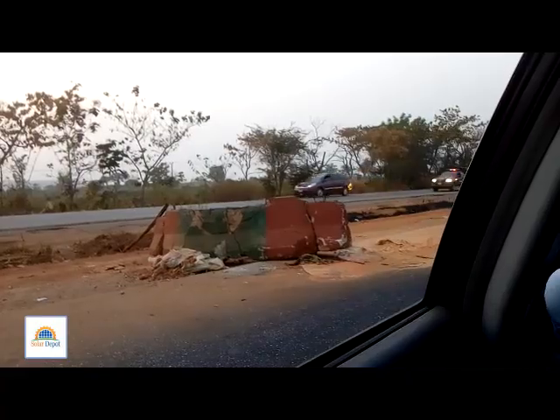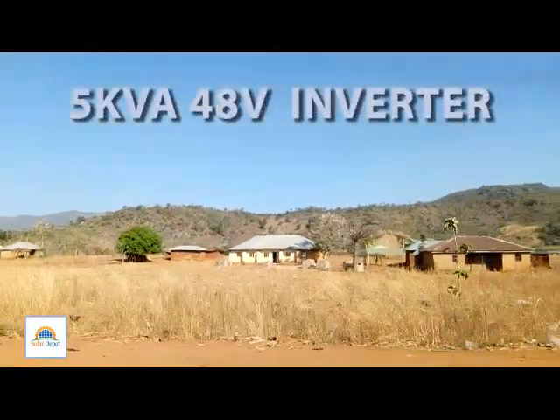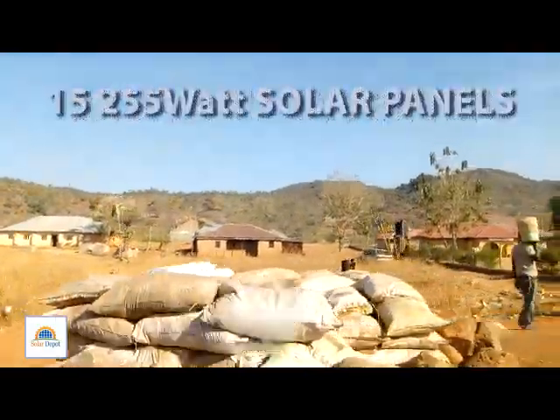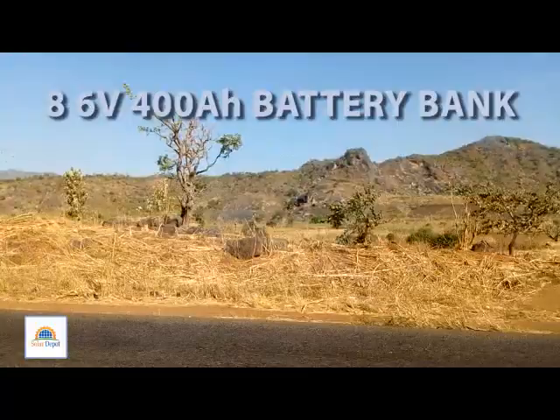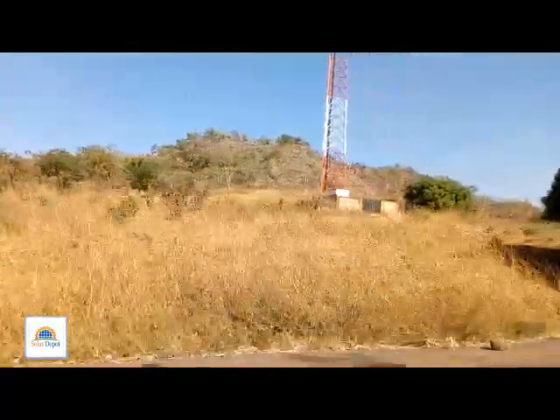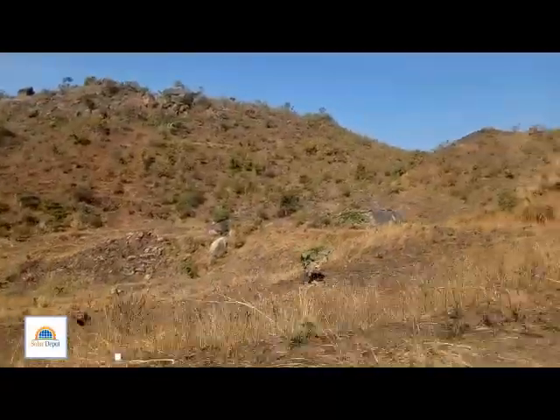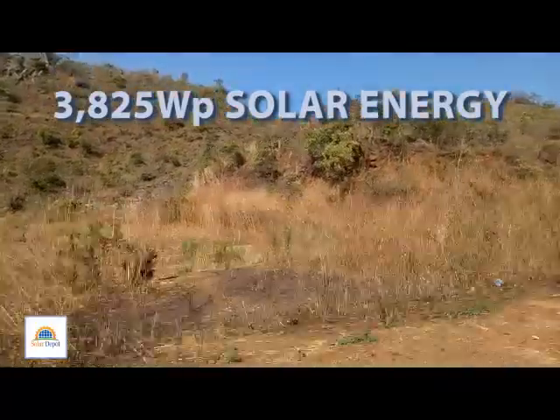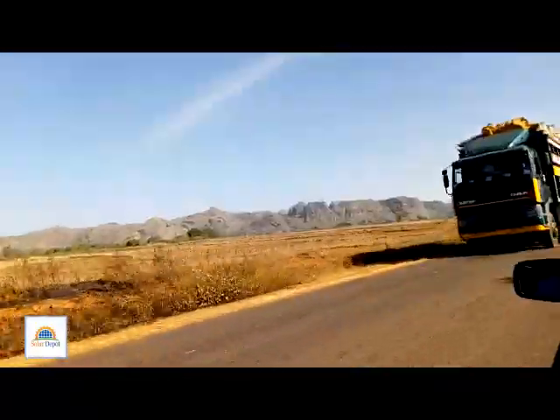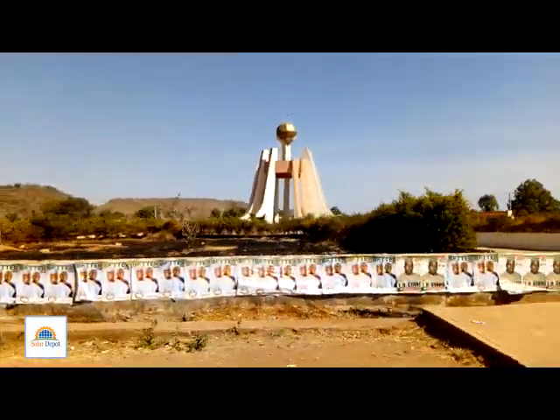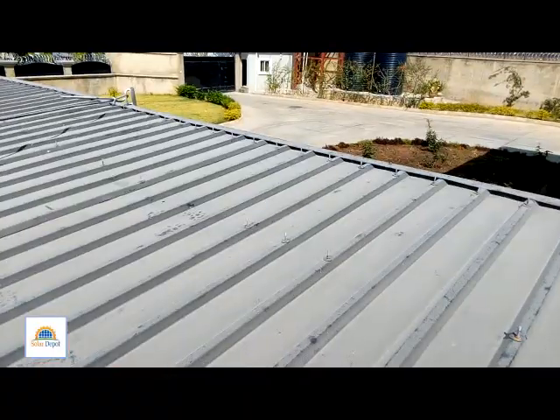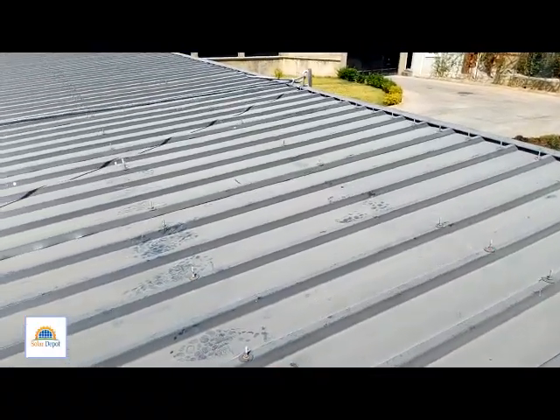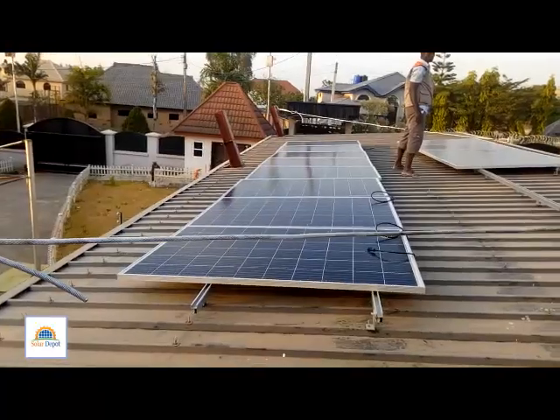This installation involves a 5 kVA 48-volt multi-plus Victron inverter, 15 255-watt polycrystalline solar panels, 8 pieces of 6-volt 400-amp-hour AGM batteries. This system is designed to capture 3,825-watt-peak capacity of solar energy to be stored in the battery bank with a total of 19,200-watt-hour capacity. The 15 solar panels are to be mounted on a carport using professional aluminum roof mounts.